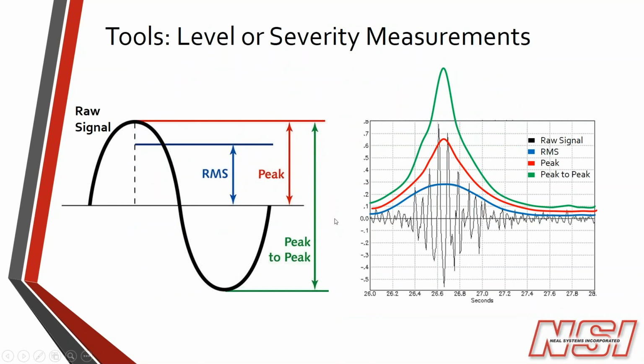And so we do have some tools, and one of the first things that people like to look at is called level or severity of the vibration. And level might be a better descriptor, but severity assumes that the level of the vibration corresponds to the condition of the machine. And certainly for a wide range of failure modes in the machine, the more they fail, the worse the condition gets, the more the vibration is going to grow and become more severe.